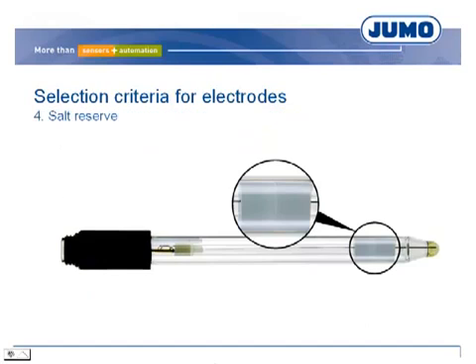The electrolyte of the reference electrode is a saturated potassium chloride solution. Depending on the application, such as ultra-pure water or highly polluted media, the salt concentration can be reduced very fast, giving the electrode a short operating life. Due to a salt reserve of salt rings, the electrolyte remains saturated, so the operating life of the electrode is much longer.